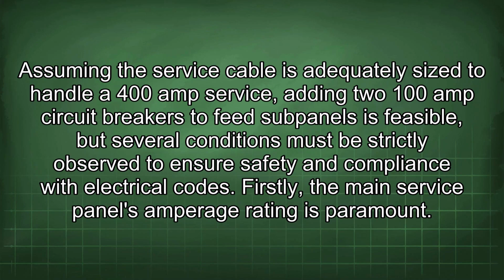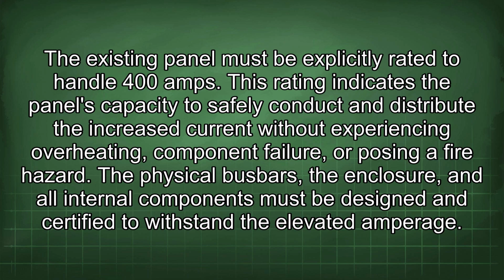Assuming the service cable is adequately sized to handle a 400 amp service, adding two 100 amp circuit breakers to feed subpanels is feasible, but several conditions must be strictly observed to ensure safety and compliance with electrical codes. Firstly, the main service panel's amperage rating is paramount. The existing panel must be explicitly rated to handle 400 amps.